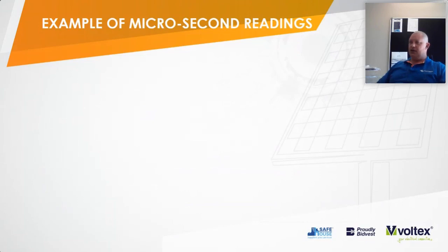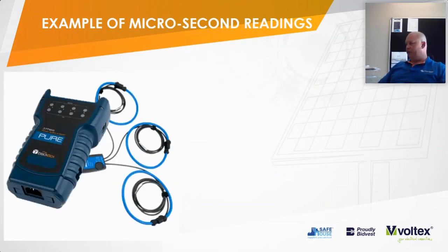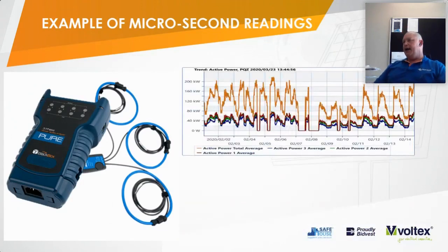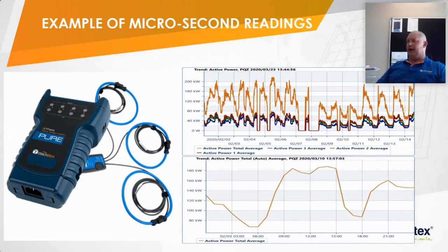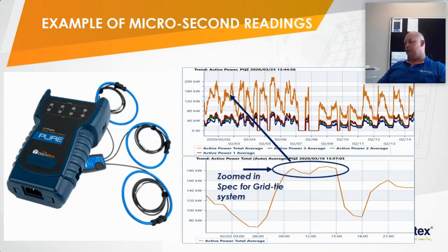Example of a microsecond energy auditor. This is the brand we prefer using. And if you look at the graphs supplied, you can zoom into microseconds to look at peaks. We literally take the averages and look at a specific time of day, usually between 6 a.m. and 6 p.m., to see what your consumption curve is. And we utilize the software to zoom in to get that specific reading. And that gives us an idea. As this specific unit, you'll see it's got an average of around about 180 kilowatt. So that is what we would spec our system according to.